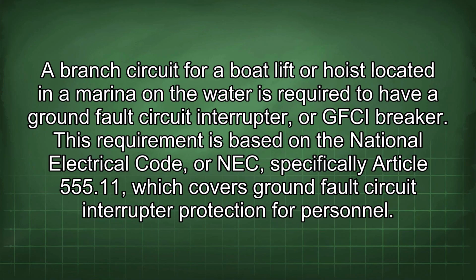A branch circuit for a boat lift or hoist located in a marina on the water is required to have a ground fault circuit interrupter, or GFCI breaker. This requirement is based on the National Electrical Code, or NEC, specifically Article 555.11, which covers ground fault circuit interrupter protection for personnel.